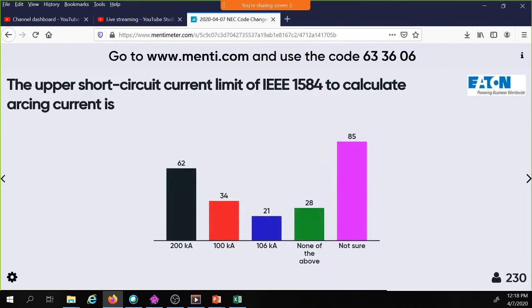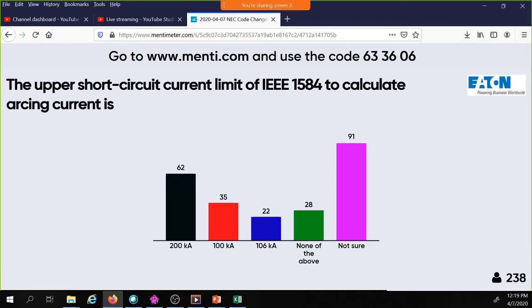It's just an interesting fact. The upper short circuit current limit of 1584 to calculate arcing current, there's a lot of not sures. And you know what? This one slapped me in the face. It was after 240.67 and 240.87 came about, and I was putting together my educational materials and trying to provide tools to our customers to apply fuses and circuit breakers. And I realized that the upper limit of IEEE 1584, out of bounds, is 106,000 amps. So there is no way for me to calculate an arcing current when my available bolted fault current is greater than 106,000 amps. We're going to talk about that. And that presents a unique issue when we're meeting 240.67 and 240.87 when your bolted fault currents are greater than 106,000 amps.